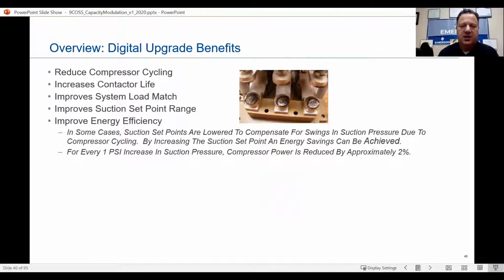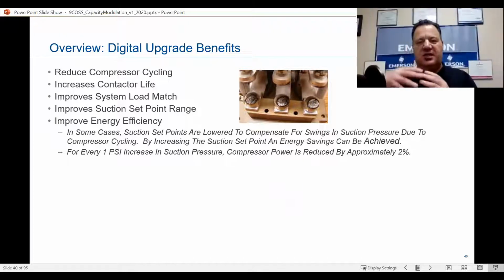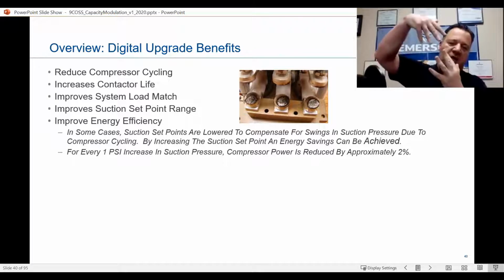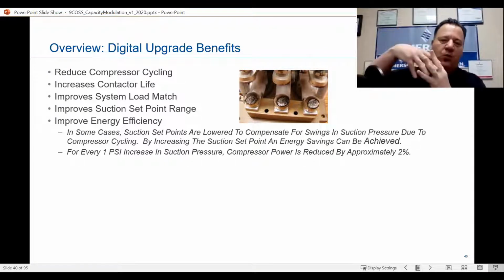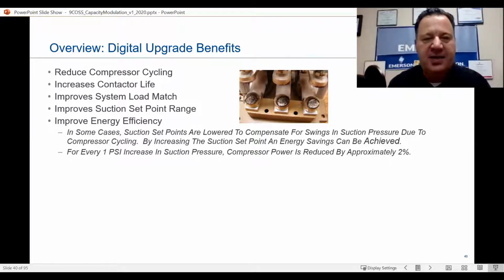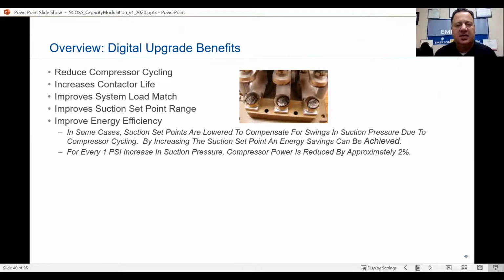Overview, the digital upgrade benefits. So instead of shutting on and off on the digital, you're actually taking those scrolls and loading and unloading, loading and unloading. Okay, you have that 1 millimeter we talked about in the anatomy of the scroll. That's sliding up, so it's matching the load, and that's really what all this modulating is about. It's load matching, right? We're trying to load match exactly whatever that control is calling for, and not exceeding that, to keep it as efficient as possible.